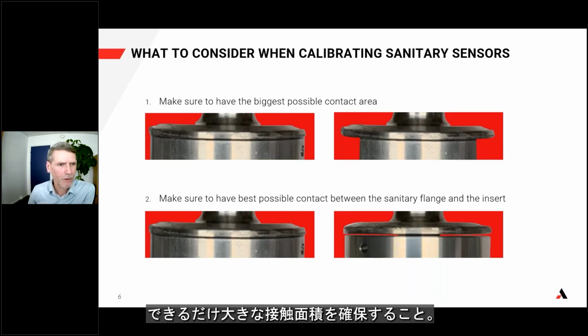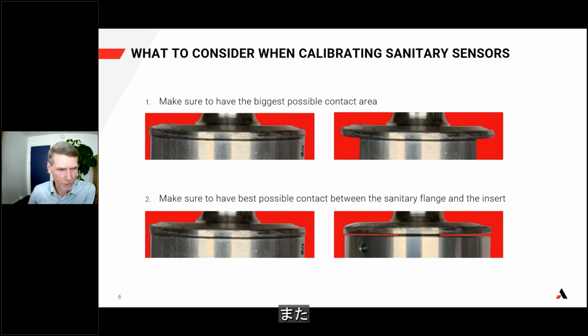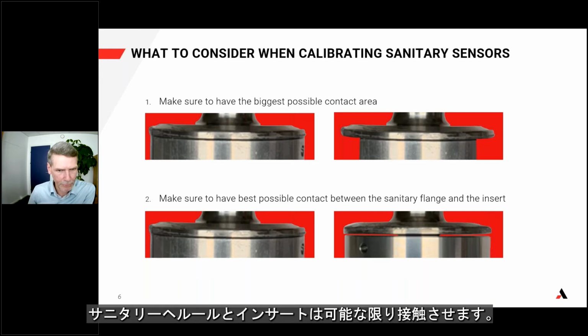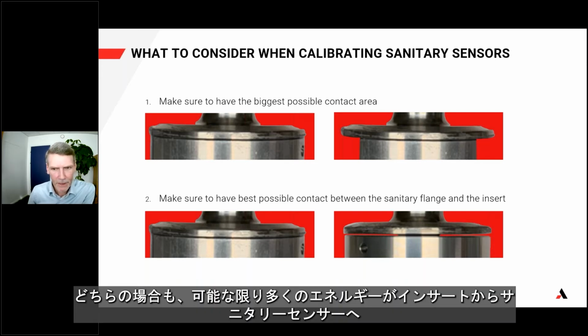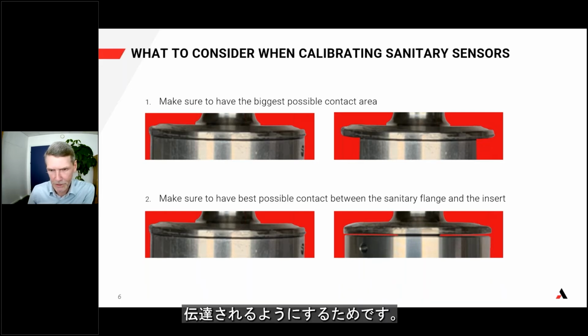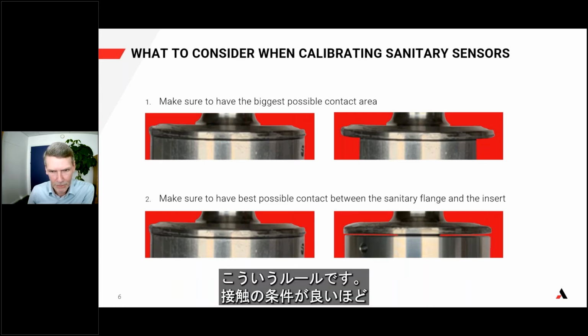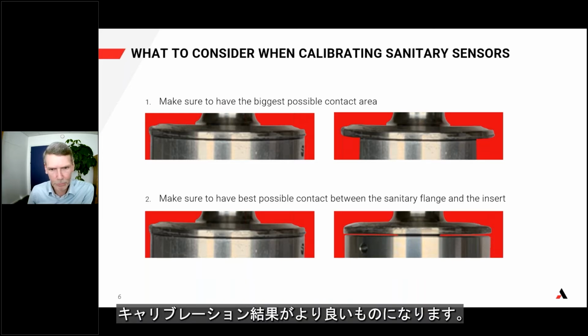Make sure to have the biggest possible contact area. Also, make sure to have the best possible contact between the sanitary flange and the insert. In both cases, that is in order to have as much energy as possible transferred from the insert to the sanitary sensor. The rule goes: the better the thermal contact, the better the calibration result will be.